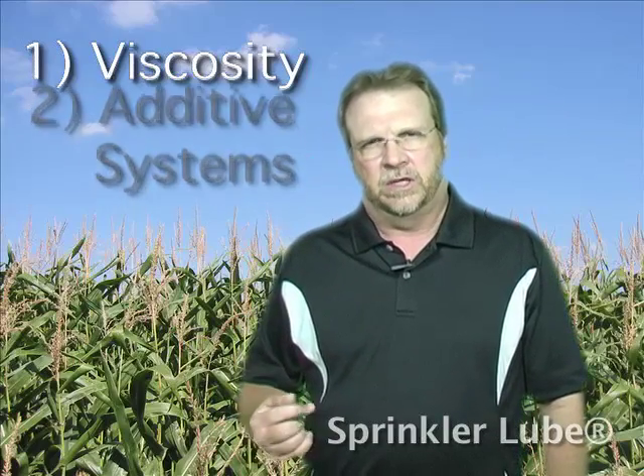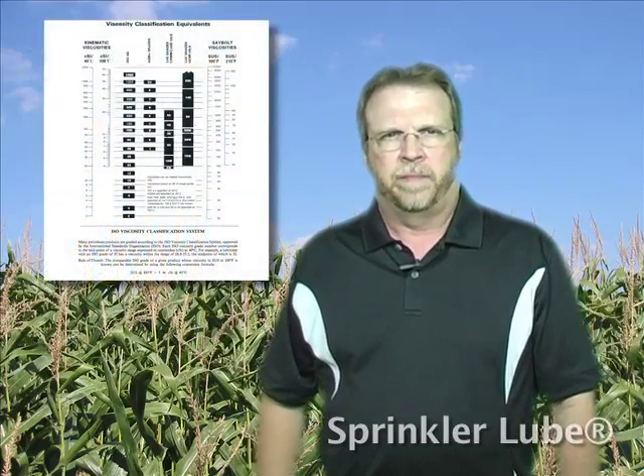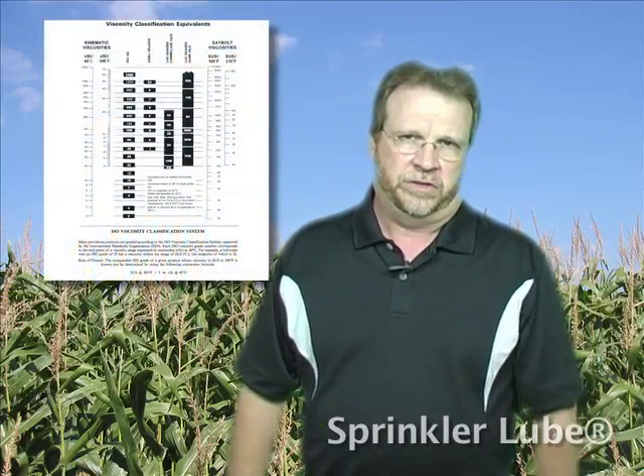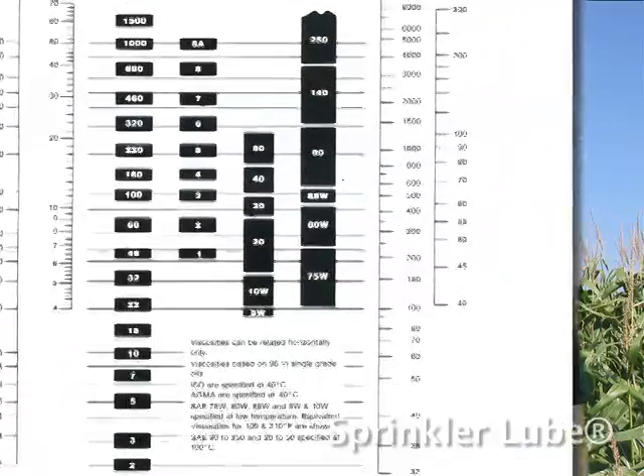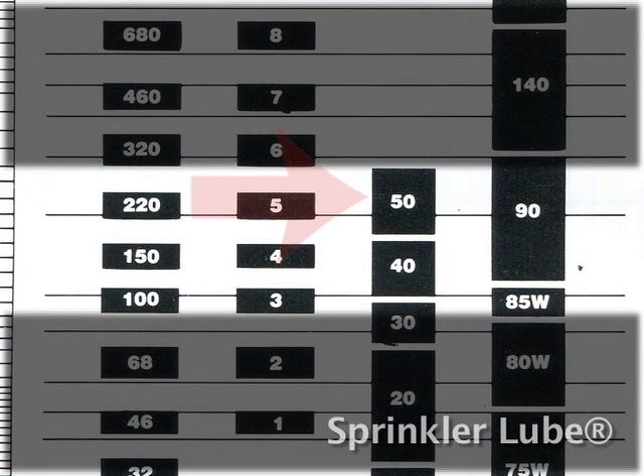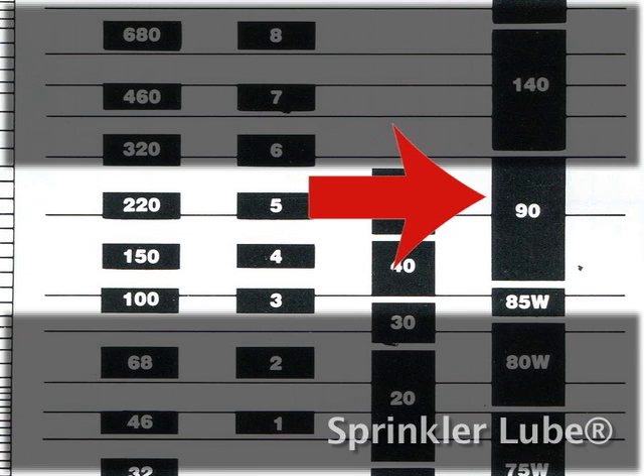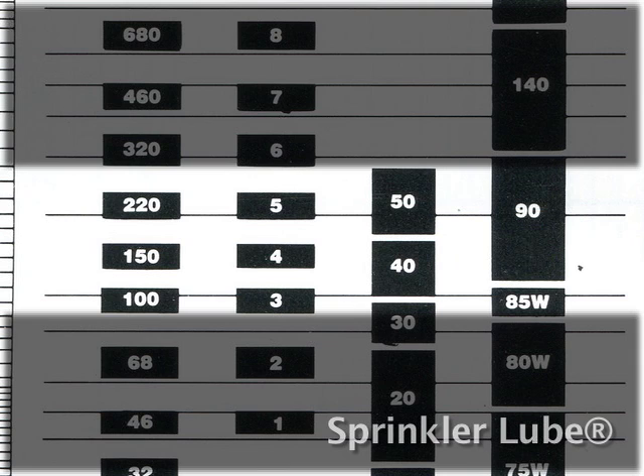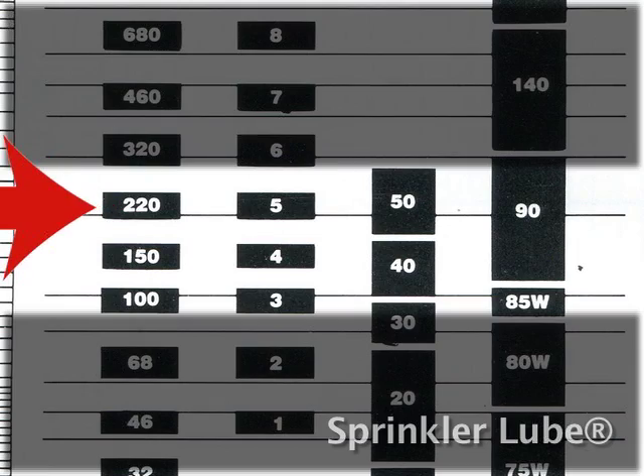Here we have a viscosity equivalence chart. My question to you: what is the difference between 50-weight motor oil and 90-weight gear oil? For the most part, the answer we hear is 40. But if you look at the SAE engine oil classification and slide across to the SAE gear oil classification, you will see that they are both in the same viscosity range. You will also see that an AGMA 5 or an ISO 220 are in the same range.